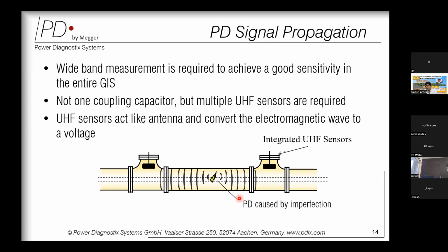Since it is a packet of pulses, it contains various frequency components which could have different attenuation or different reflection, and hence our measuring instrument should have a wide band measurement. It should not be measuring a particular frequency spectrum, but should be a wide band measuring instrument providing good sensitivity to the entire GIS. That means the measurement bandwidth should be from 100 megahertz to 2000 megahertz.